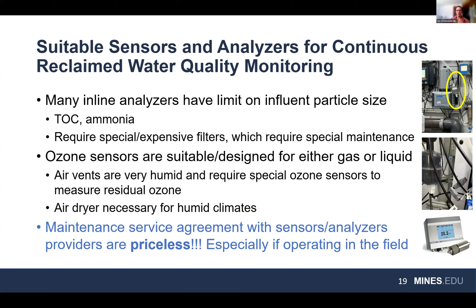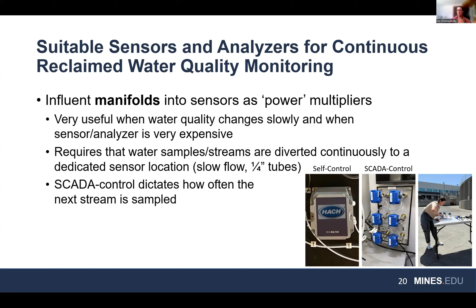Bringing back the manifolds—we built this in the field and it ended up working really well. We have a TOC analyzer that can only analyze one stream at a time, and this manifold, in combination with our SCADA control system, can open and close different valves to pull samples from different parts of the process.